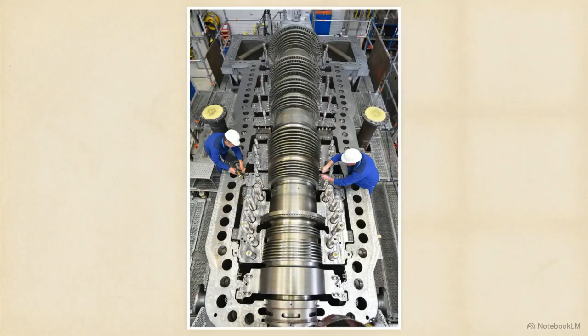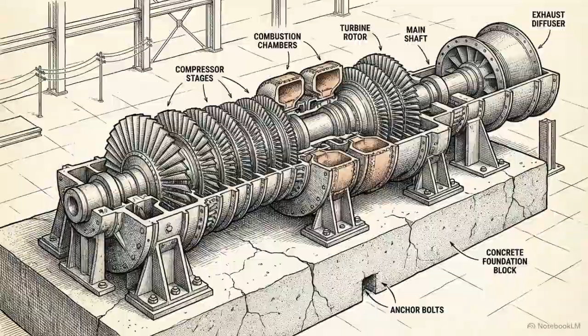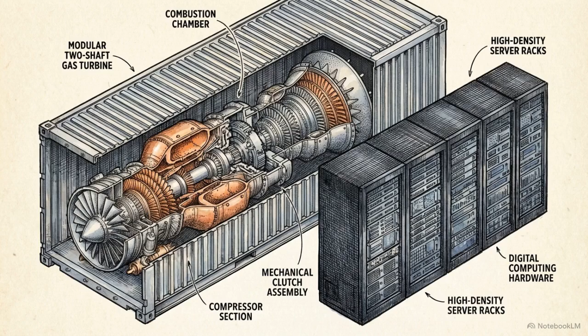Gas turbines act as an instant-on firming shield, providing the immediate grid stability that prevents AI clusters from crashing during sudden power fluctuations. Utility-scale macro power relies on massive single-shaft turbines to provide heavy grid inertia, whereas edge data centers use micropower, agile two-shaft turbines that act as a mechanical clutch to quickly ramp up and down.